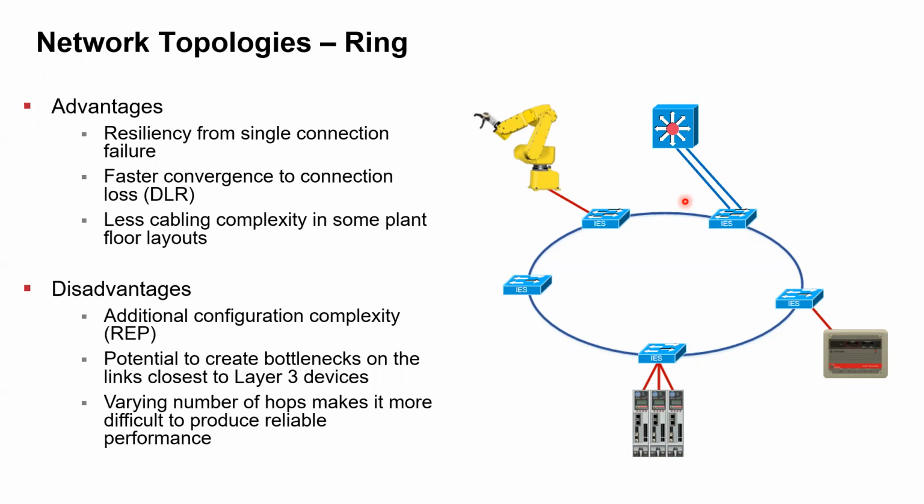And it's heavily tested up to 50 nodes in the network. So it's something we know the outcome of if you use this network; it's a very robust, easy to implement network. Yeah, good point. That's one of the disadvantages: there's a varying number of hops. So there is a limit, of course, and like we said, life is full of trade-offs. There's a published limit to the number of devices you can put into the ring, so just be aware of those design criteria before you implement.